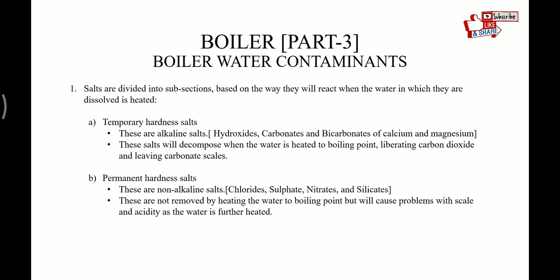Salts are divided into subsections based on the way they react when the water in which they are dissolved is heated. First is temporary hardness salt and the other is permanent hardness salt. Temporary hardness salts are alkaline salts — hydroxide, carbonate, and bicarbonate of calcium and magnesium. These salts will decompose when water is heated to boiling point and liberate carbon dioxide, leaving carbonate scales. Permanent hardness salts are non-alkaline salts: chloride, sulphate, nitrates, and silicates. These are not removed by heating the water to boiling point but will cause problems with scale and acidity as the water is further heated.